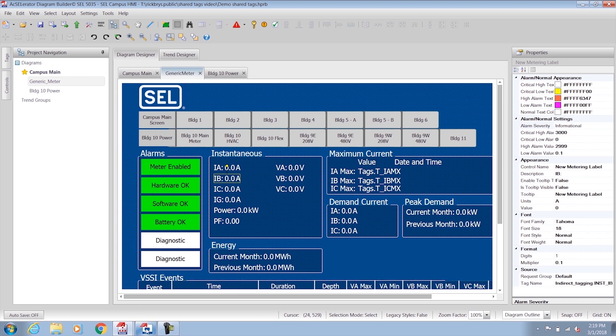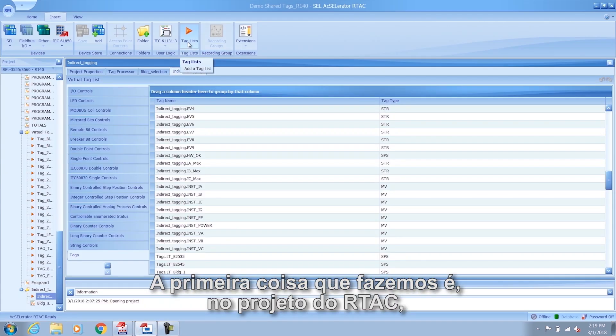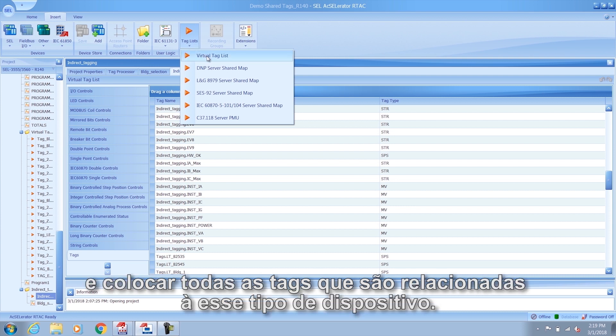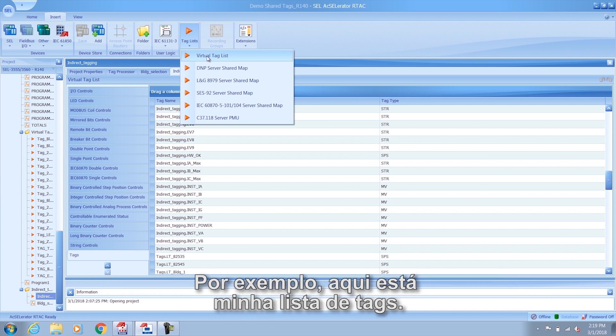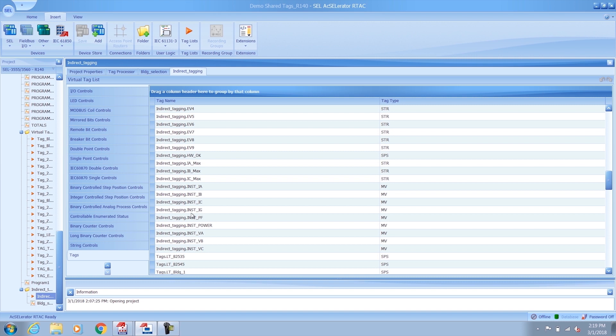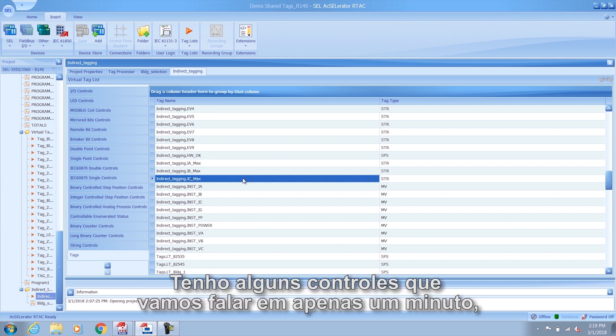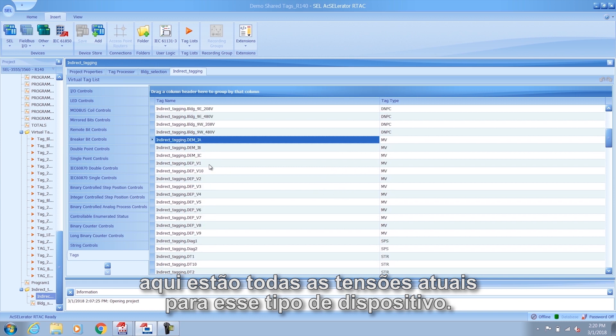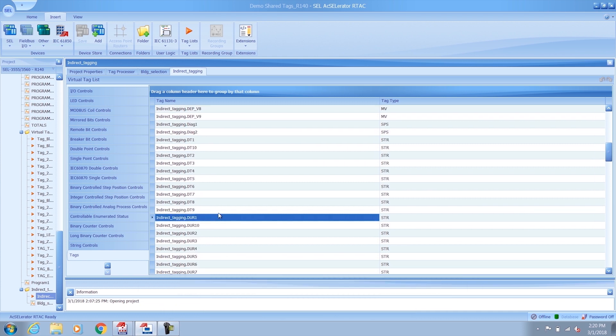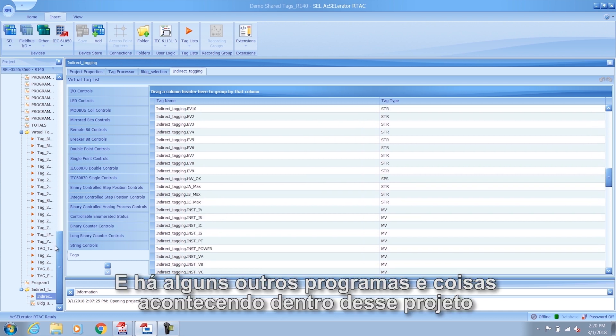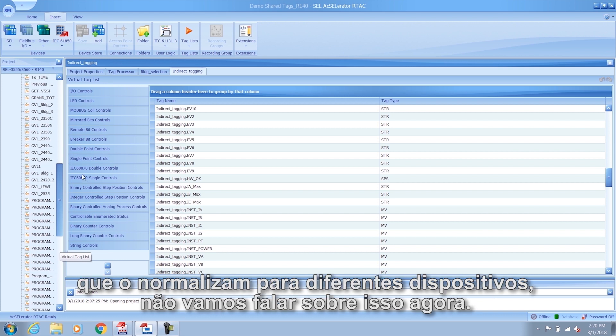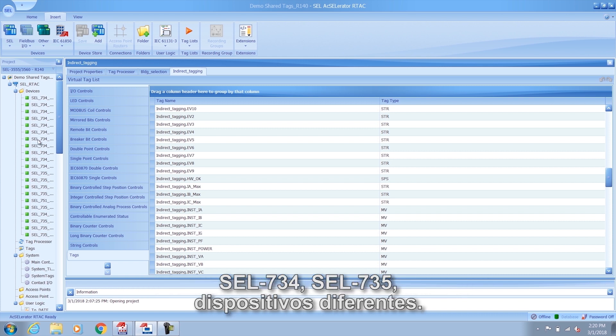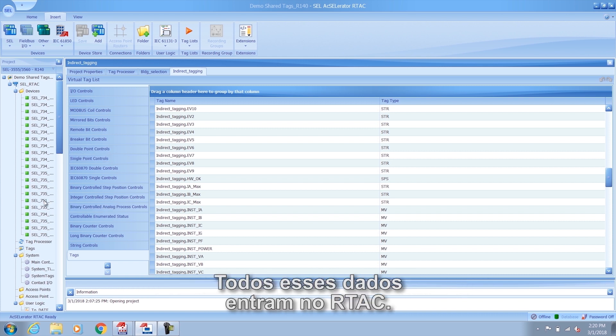So how does that work in the RTAC? The first thing we do in the RTAC project is create a virtual tag list and put all of the tags related to that kind of device. Here's my tag list — I have some controls we'll talk about in a minute, but here are all the currents, voltages, and everything for that device type. There are also some other programs inside this project that normalize it for different devices. Here are all the devices being pulled — 734s, 735s, different devices — and all of that data goes into the RTAC.